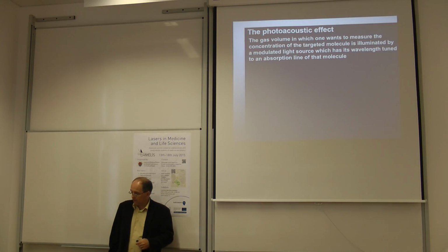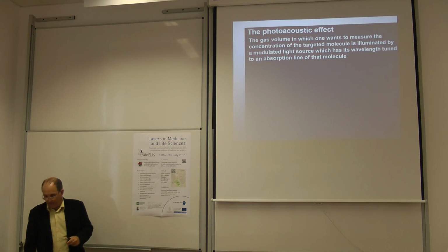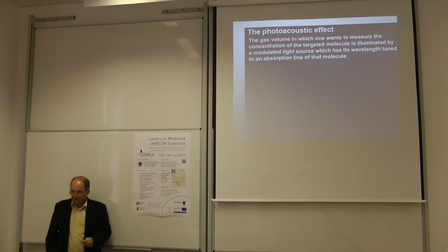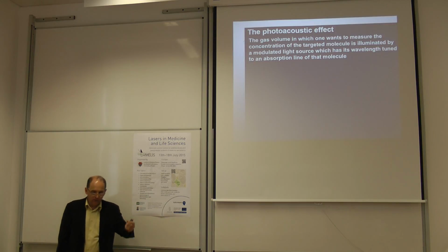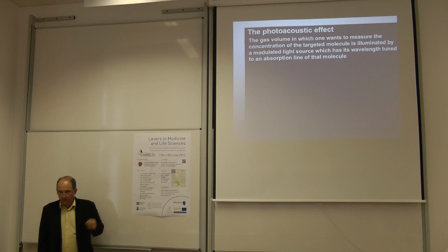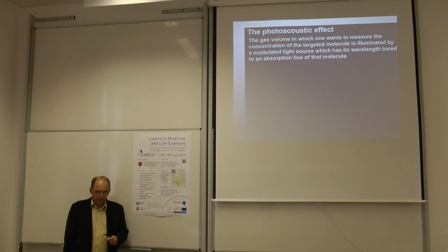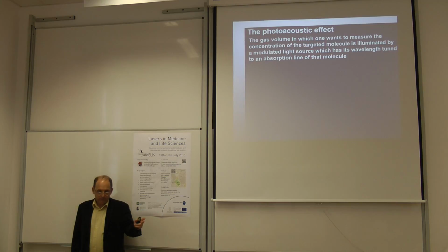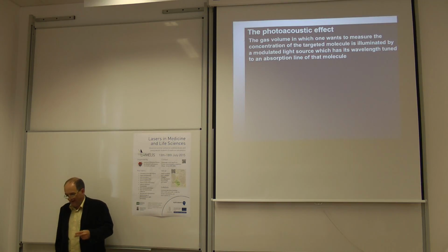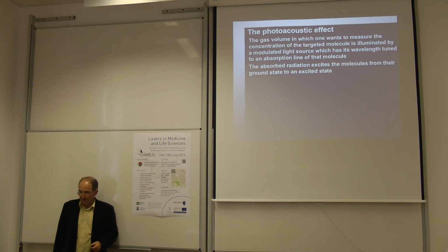The photoacoustic effect is very simple. You have a gas volume in which you want to measure the concentration of the targeted molecule you are interested in. You illuminate this volume with a light source which is modulated in time, and the wavelength of this light source is tuned to an absorption line of the molecule you want to detect.